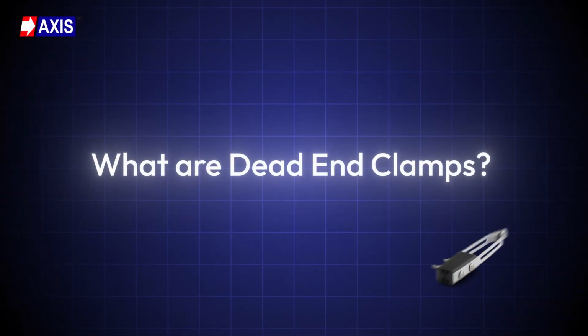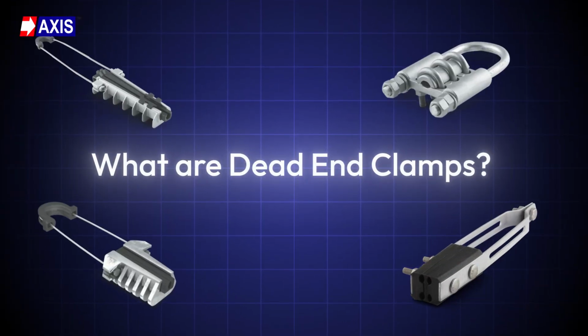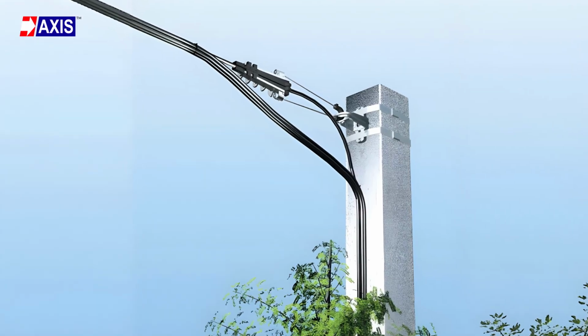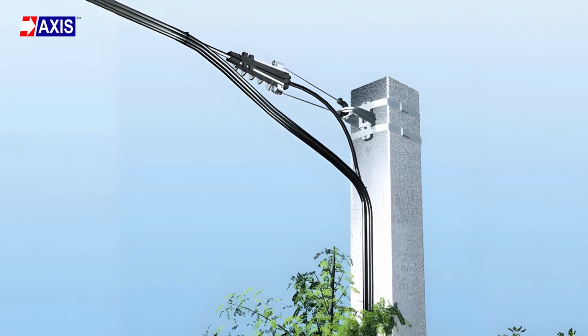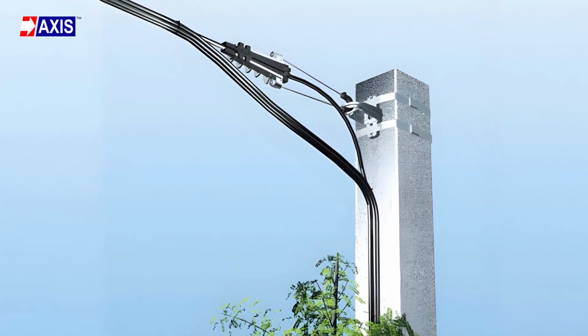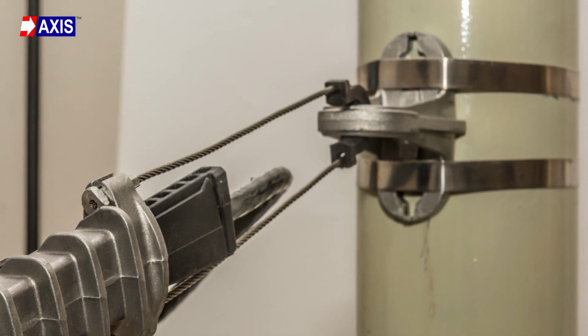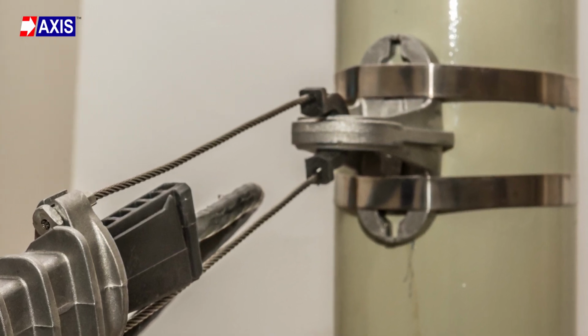First, let's briefly discuss dead-end clamps and their usage. Also known as anchoring clamps or tension clamps, these components are used to strain the insulated neutral messenger in a low-voltage aerial bundle cable system. They help in providing tension and direction to the cable at angles and endpoints without damaging the insulation. To function properly, this dead-end clamp is installed along a bracket or other support hardware depending on the layout and design requirements. This makes it a customizable solution for different installation scenarios.